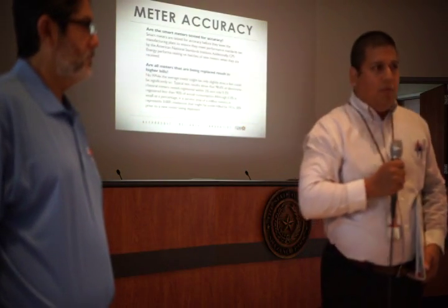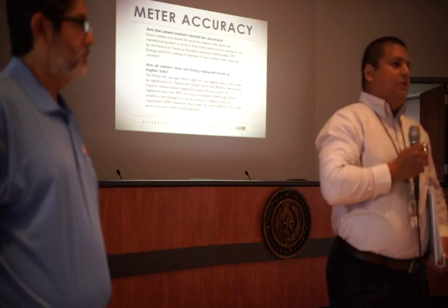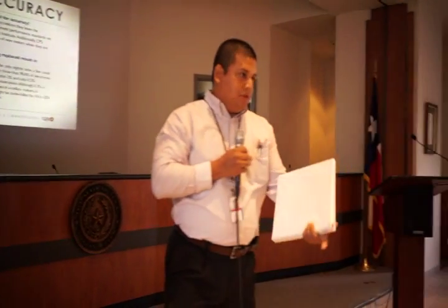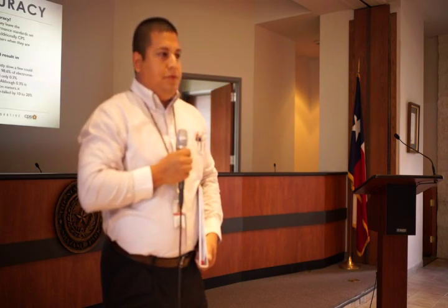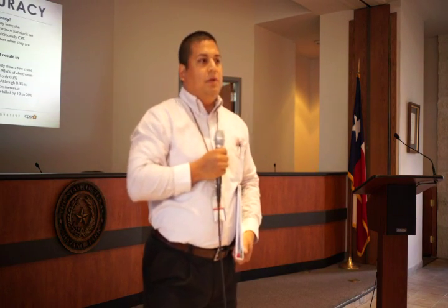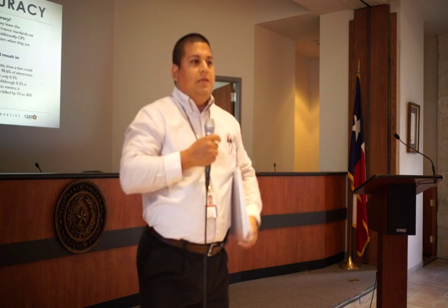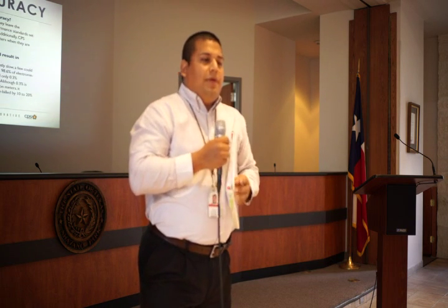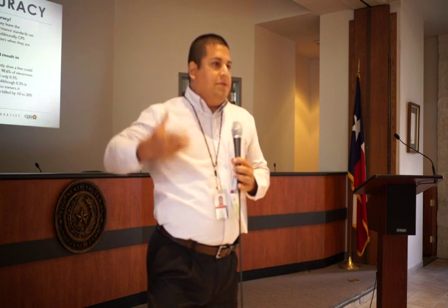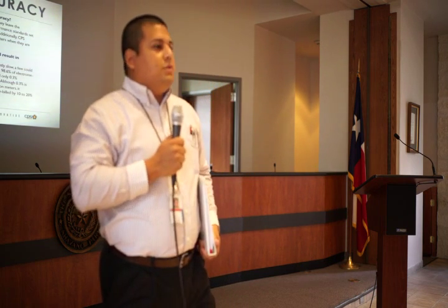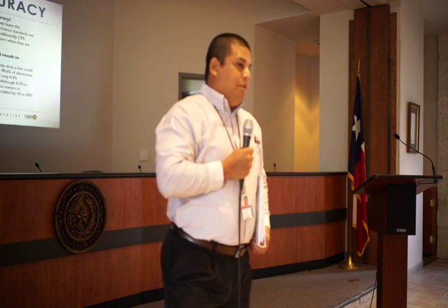Okay. So we have drive-by meters and we have smart meters. And I like to tell customers that the meters are the same. The metrology board that actually does the measurements for the power used by the customer is the same metrology board that's in the AMI meter. The only difference is the smart meter has a communication module that reads the metrology board and sends that information back to CPS Energy. So in essence, they're all smart. We just have a different way of reading the meter.